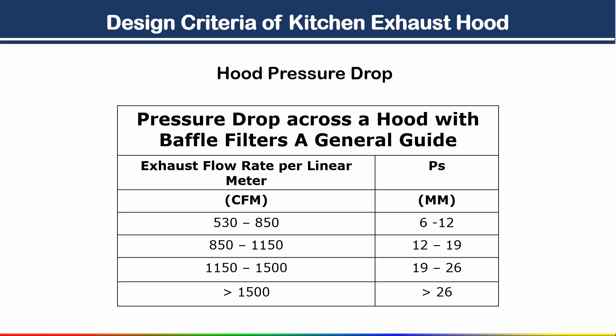Now let's see the hood pressure drop. Based on your exhaust flow rate per linear meter, you get the pressure drop. If the flow rate is between 530 to 850 cfm, the pressure drop is 6 to 12 mm. This is the pressure drop across the hood with baffle filter.